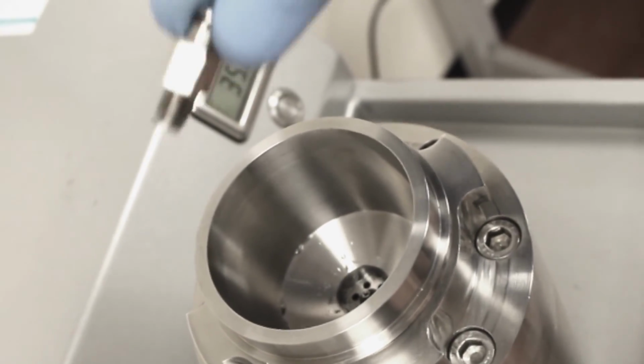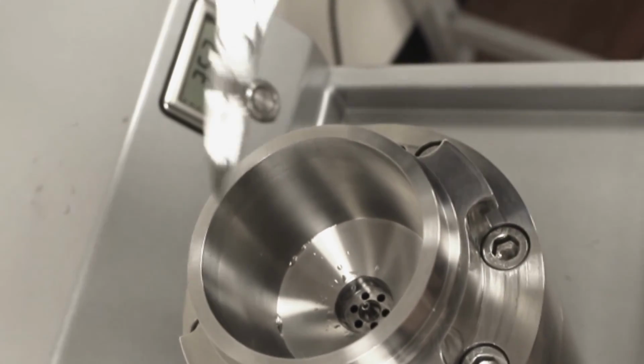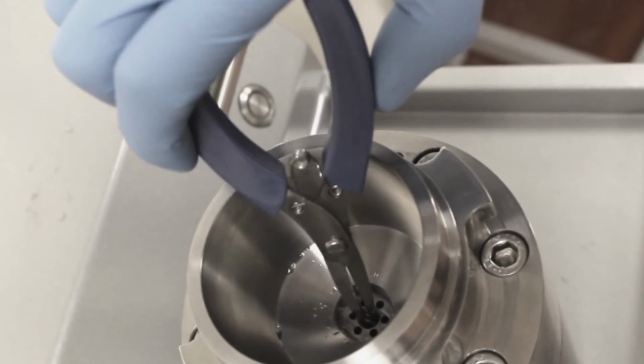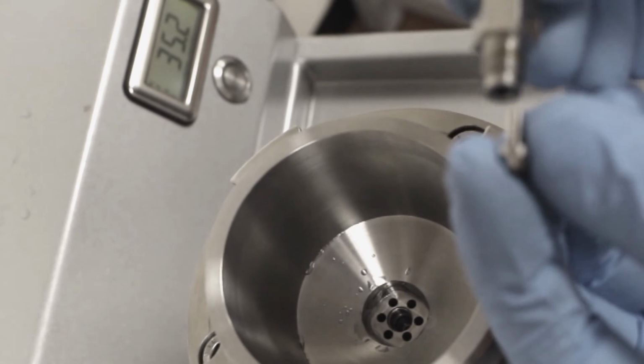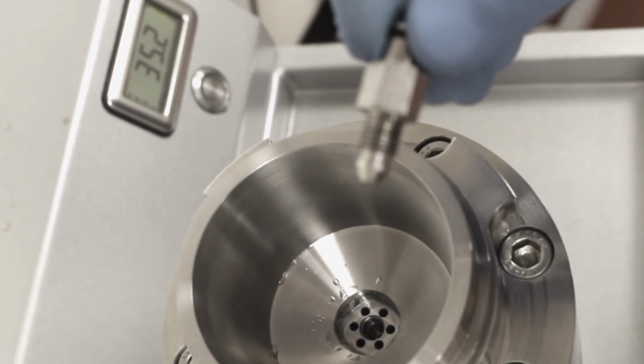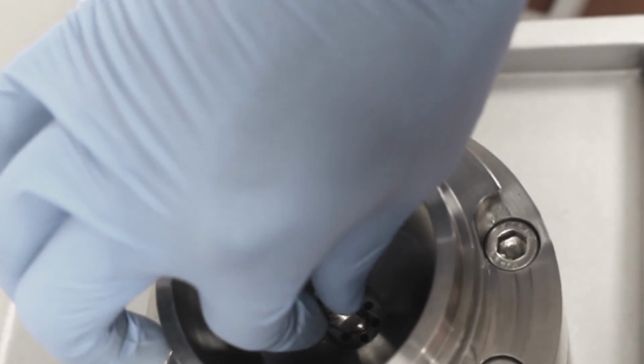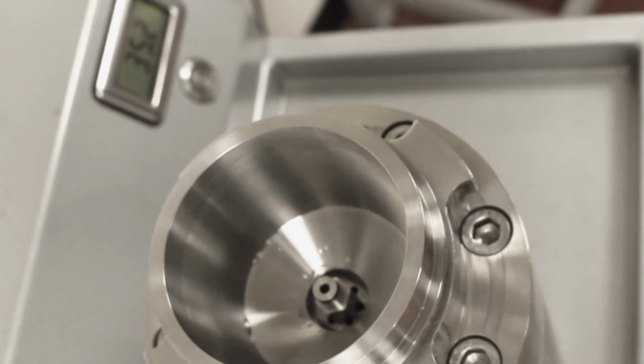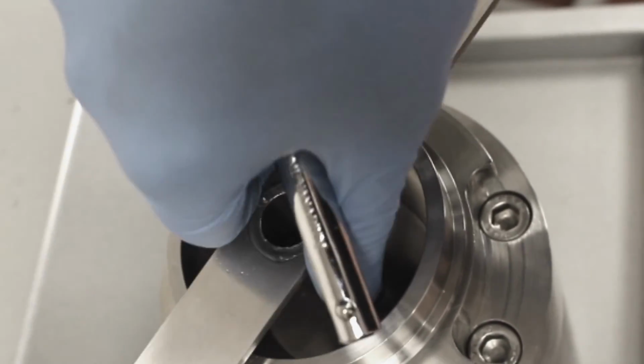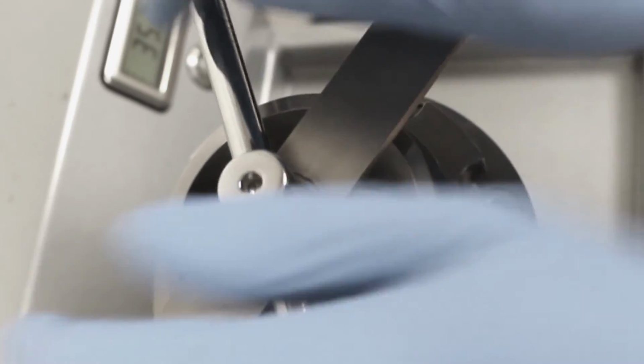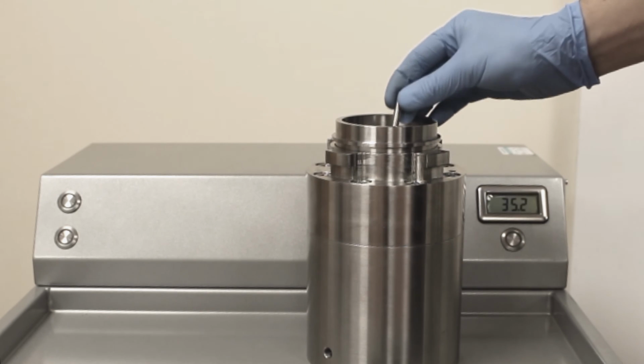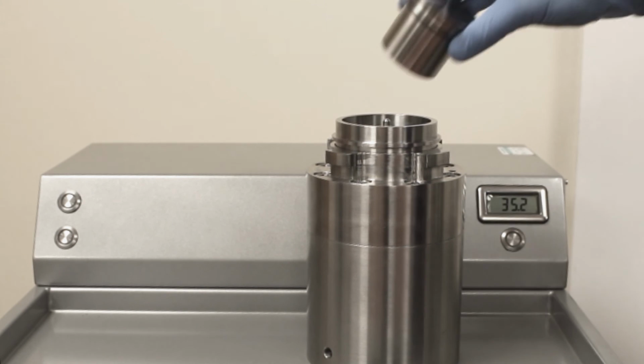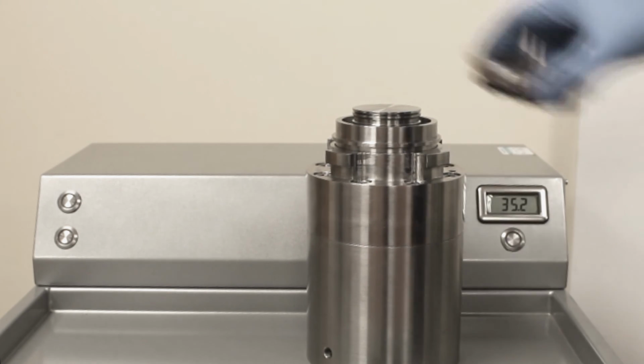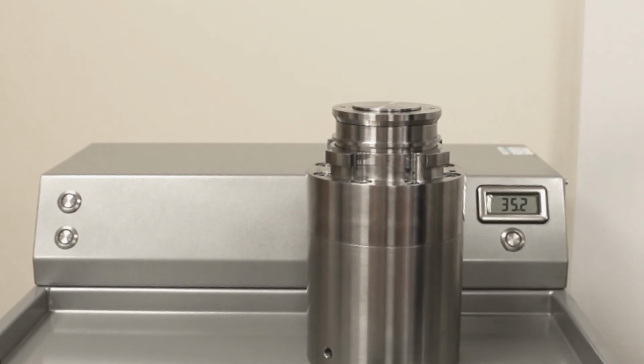Remove the jet retainer and using the pliers, remove the jet. To replace the jet, slide the shaft of the jet into the jet retainer and screw the jet retainer into the outer cup. Tighten using the square drive and the 11mm and T-bar. Refit the anti-foam pin, the inner cup assembly, the outer cup lid and the main lid.